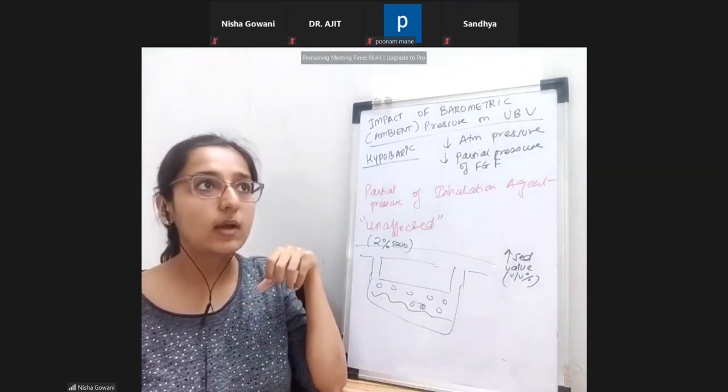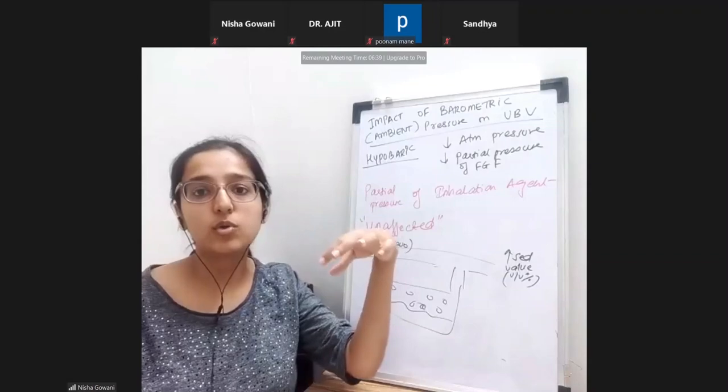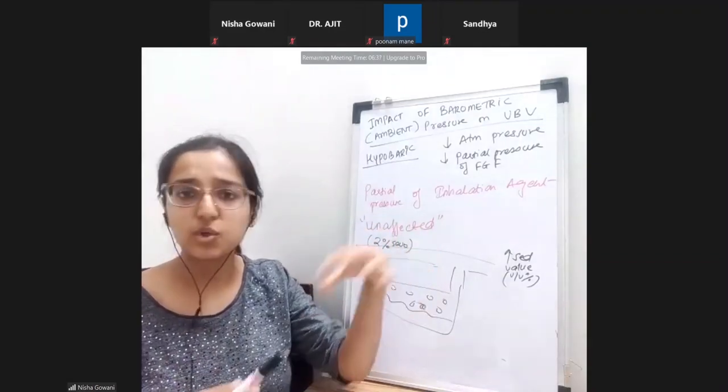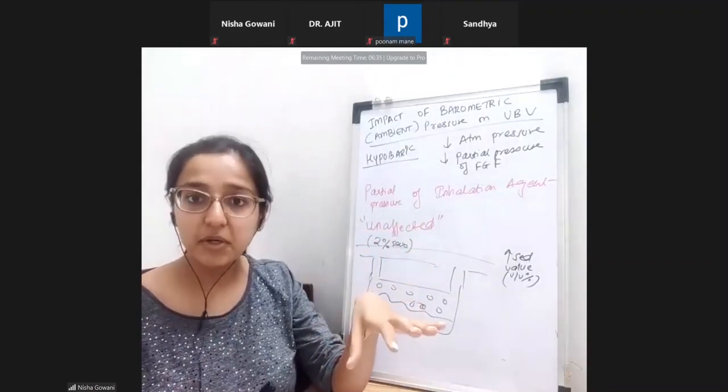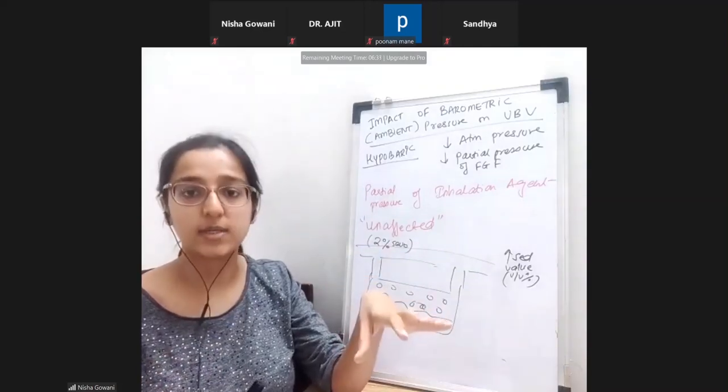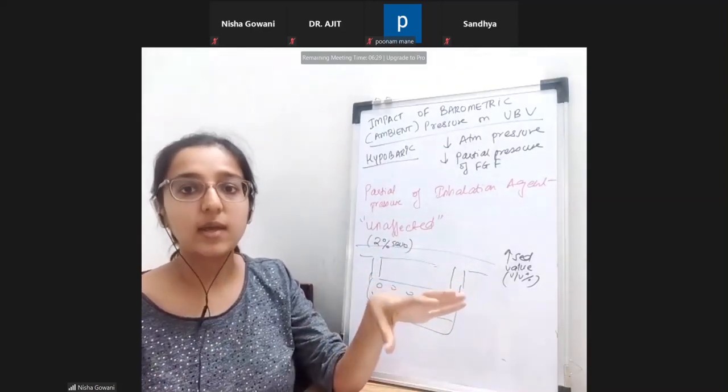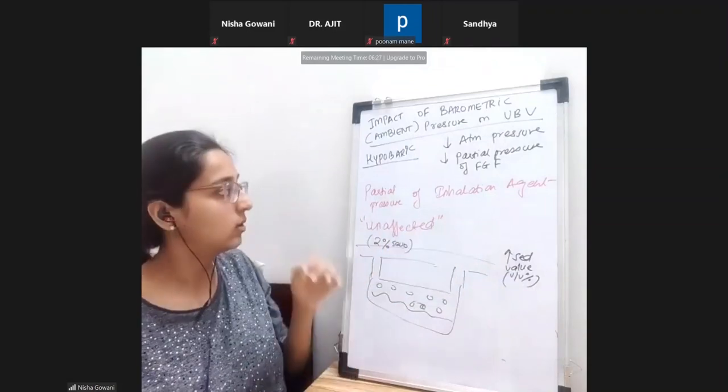You don't have to think, okay, I'm at a higher altitude, let me reduce or increase. We'll understand that later, so you don't need to do that. If you want to deliver 2% sevoflurane, you set it at 2%. You don't need to alter that. And we'll understand why we don't need to alter.